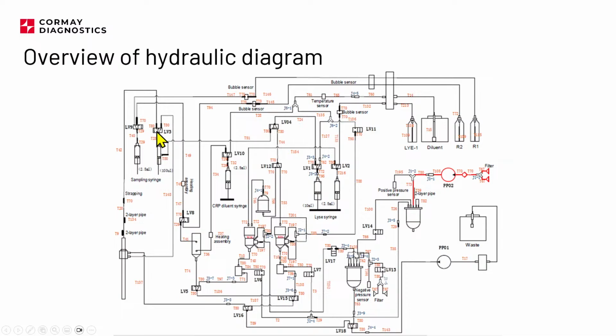Another thing which is important here is that the analyzer also needs to rinse the inside of the sampling needle. Since the volume of this syringe is very small, just 100 microliters, the volume of the diluent here will not be sufficient to rinse the whole internal volume of the sampling needle. So this is the reason why we have this port here, because the analyzer can use the pressure of the 10 milliliter syringe to rinse the internal of the sampling needle.